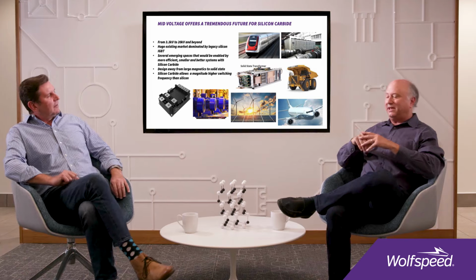Yes, so if you're going to do a 10 kV power module, you've got to have an isolation voltage of 15 kV — you can't have any partial discharge.